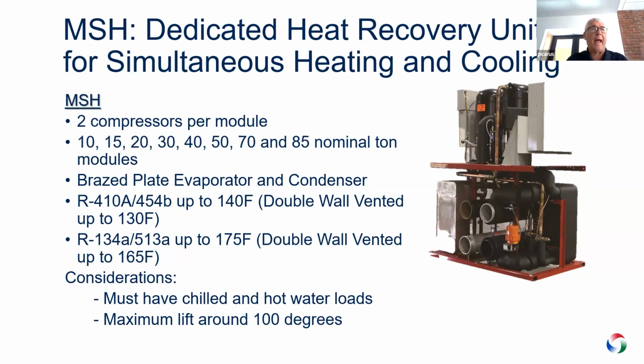Most people don't have that kind of simultaneous application. They're typically more in the 100 to 200-ton dedicated heat recovery machine. But it's essentially the same machine, designed to manage the load capabilities that are required in a facility. Same temperatures here, 410A and 454B, 140 degrees Fahrenheit, and 134 and 513A up to 170, 175 degrees in a heat recovery machine.